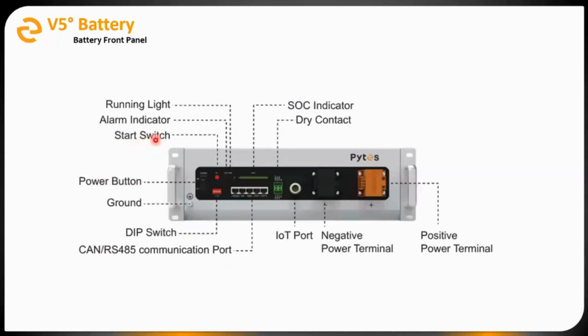We have a start switch, which is used to take the battery system in and out of operating mode and standby mode. Each battery case has a grounding lug to ground the case of the battery. Here are the dip switches, which we use to set inverter communication protocols. We've got all of our communication ports right here: CAN, RS-485. There's a console port, which we use to connect the battery to a computer for further diagnostics.